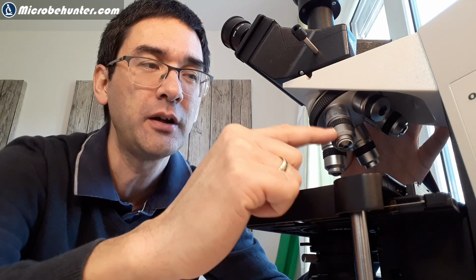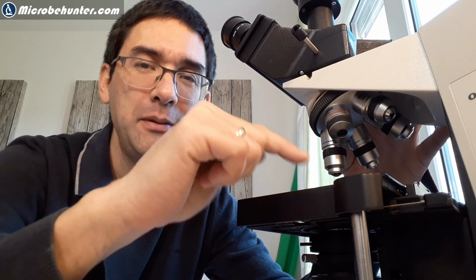Okay, so one of the problems when you mix objectives together is that they might fit. They're the same standard in many cases, 160 millimeters, but they might not be parfocal. And parfocality means that you do not have to refocus when you change the objective. That's kind of important, especially for the high magnification ones, because if they're not parfocal, when you rotate the objective into position you might end up crashing the objective into the slide, and it's not as convenient.